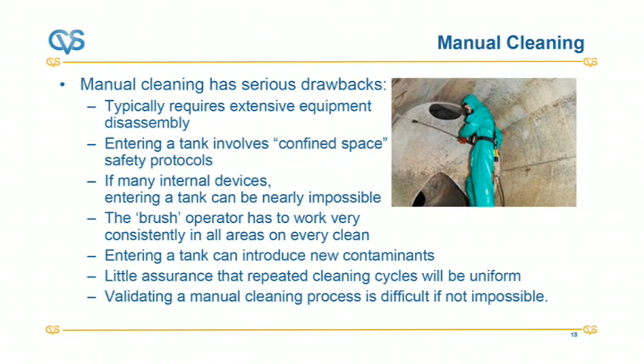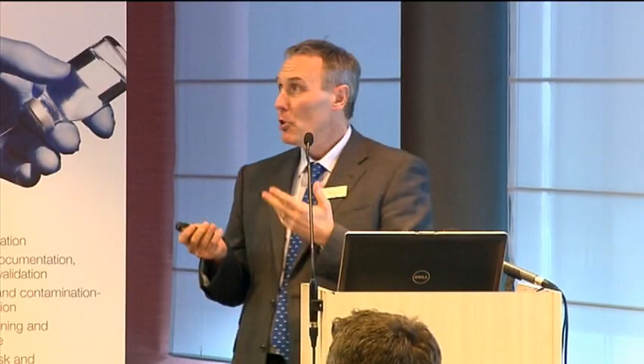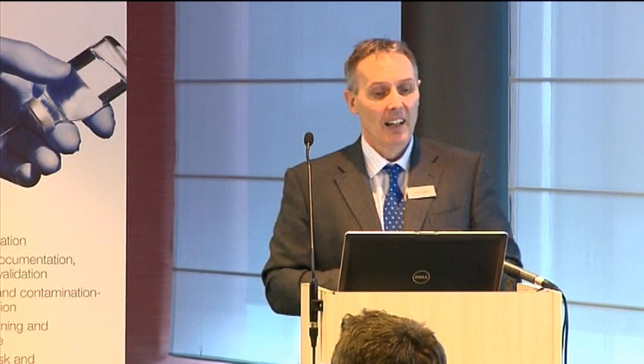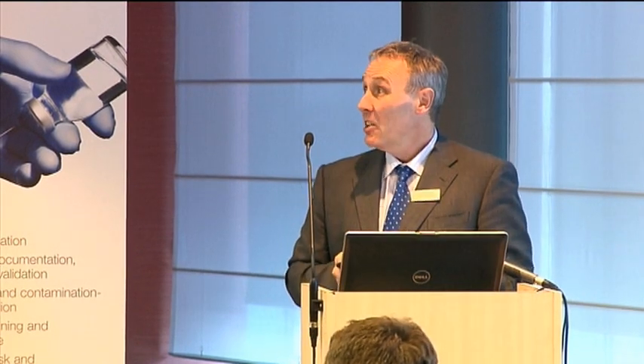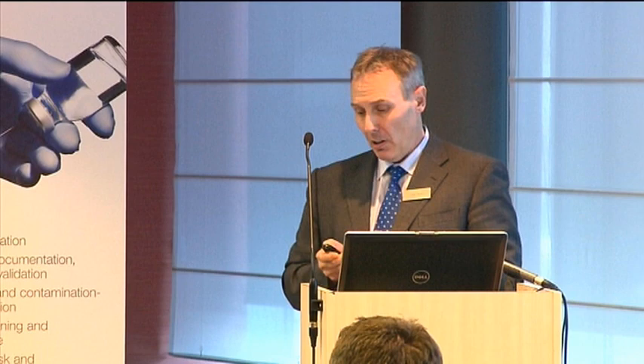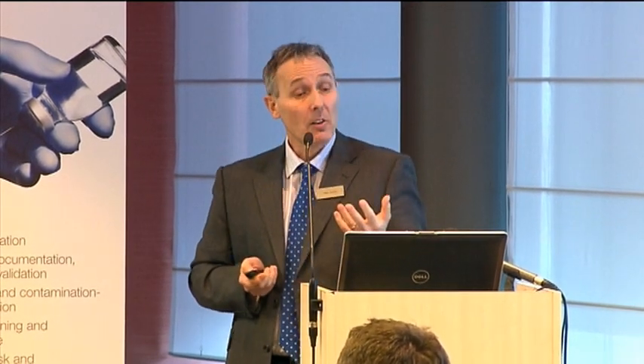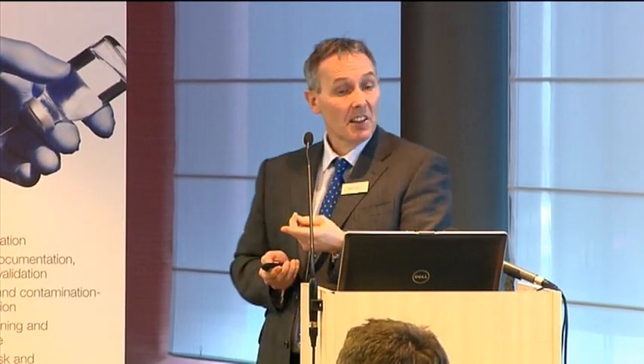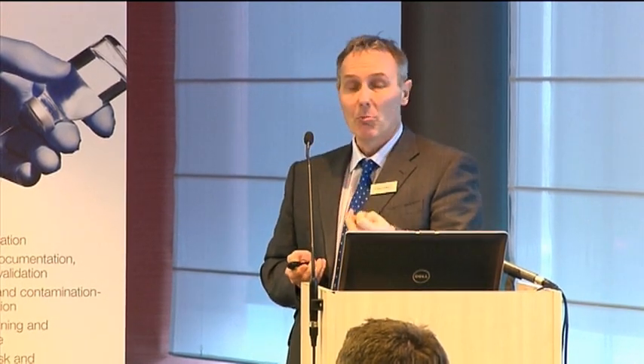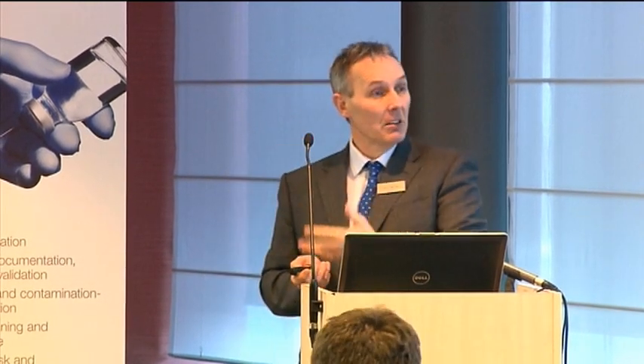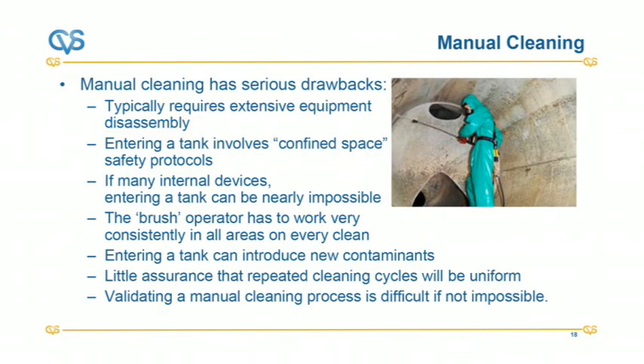If you've got many internal devices inside there, like baffles, agitators, it's going to be very difficult to actually clean it manually. And the operator, I use brush operator, that's if he's got a brush and he's cleaning, has to work very consistently in all areas on every clean to do it properly. And if you've got manual cleaning, then you're going to have to do a lot more testing, a lot more training, and a lot more retesting and monitoring. So the costs actually carry on just building up. But more fundamentally, you cannot always guarantee it's clean.